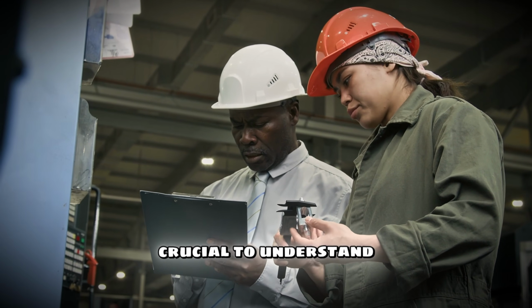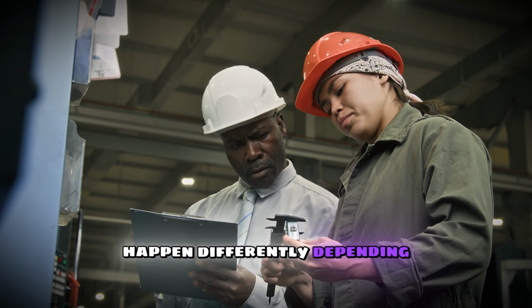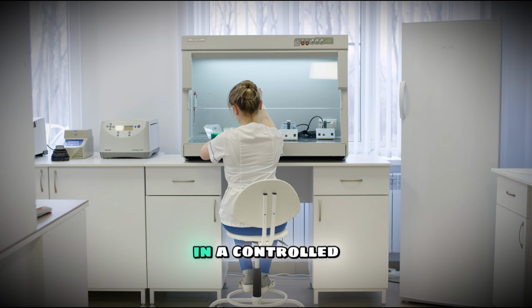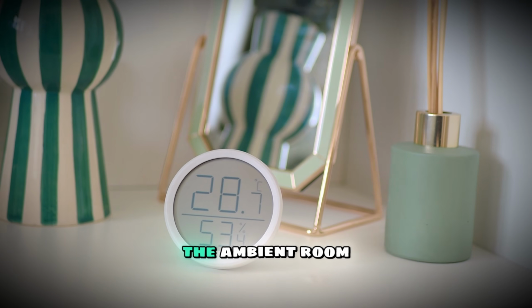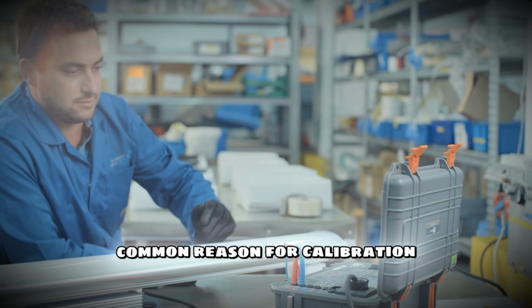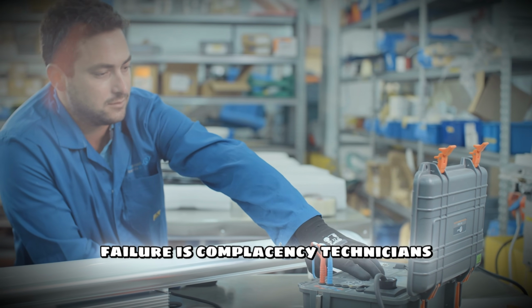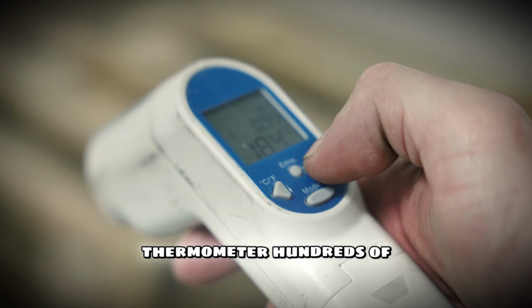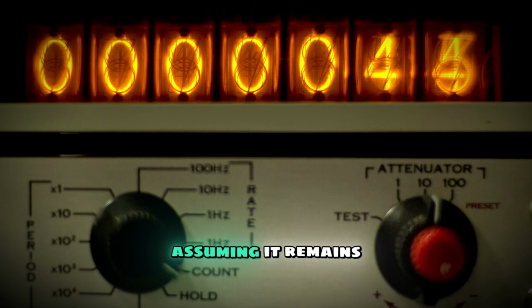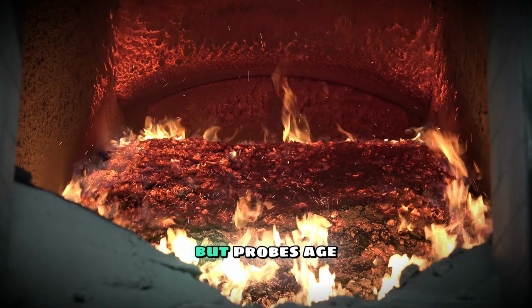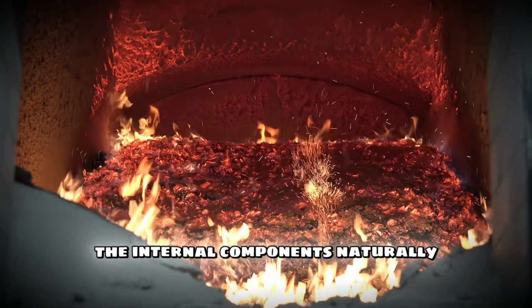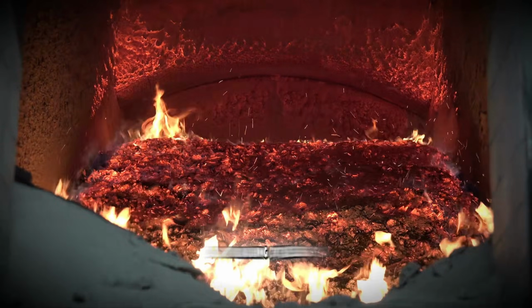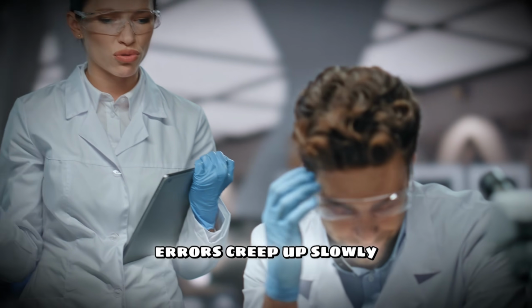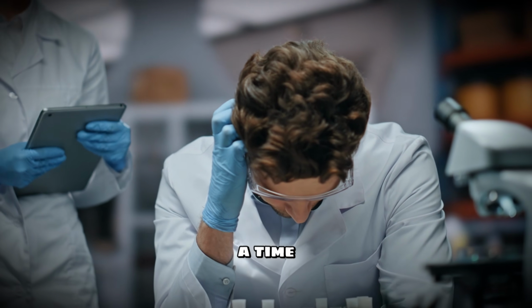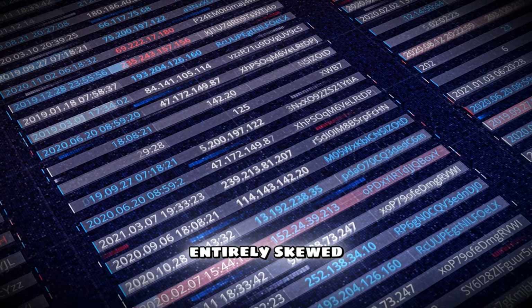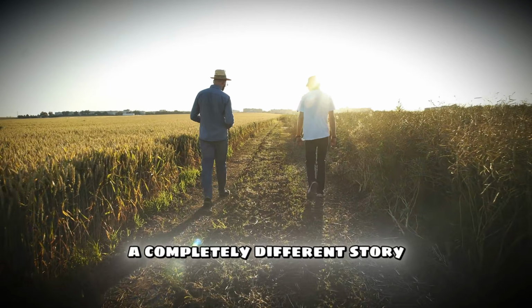It is also crucial to understand that calibration errors happen differently depending on where you are working. In a controlled laboratory environment, the ambient room temperature is stable. Here, the most common reason for calibration failure is complacency. Technicians use the same thermometer hundreds of times a month, assuming it remains perfectly calibrated indefinitely. But probes age. The internal components naturally degrade over thousands of heating and cooling cycles. In the lab, errors creep up slowly, a fraction of a degree at a time, until one day your data is entirely skewed.